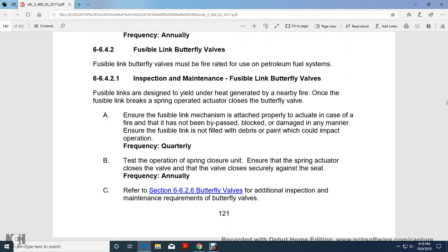Fusible link butterfly valves. Fusible link butterfly valves must be fire rated for use in petroleum fuel systems. Inspection and maintenance of fusible link fire butterfly valves. Fusible links are designed to yield under heat generated by a nearby fire. Once the fusible link breaks, the spring-operated actuator closes the butterfly. Ensure the fusible link mechanism is attached properly to actuate in case of a fire and has not been bypassed, blocked, or damaged in any manner. Ensure the fusible link is not filled with debris or paint which could impact the operation, quarterly. Test the operation of the spring closure unit. Ensure the spring actuator closes the valve securely against the seat annually.